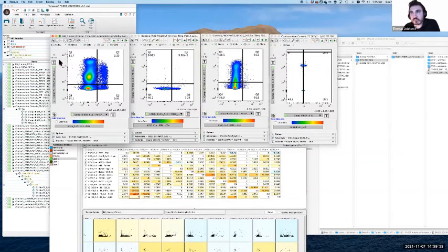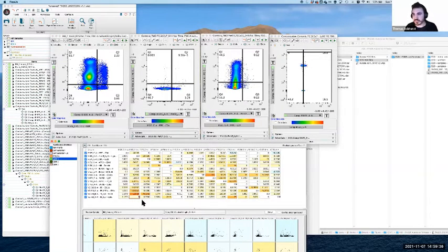Now, in this case, this is reasonably simple. If we went the other direction, say we turned it up too high, they would all be leaning over to the left. So the starting value, what did I say it was, 4, something like that? Yeah, so 4 was clearly too high. Typically, we'd walk it down progressively until we can see that we've corrected what this signal looks like. But importantly, we're doing it with reference to the FMO and to the single stain.